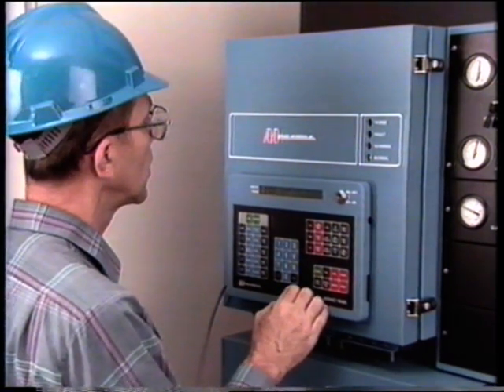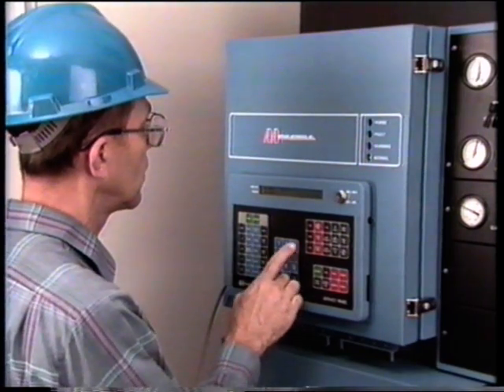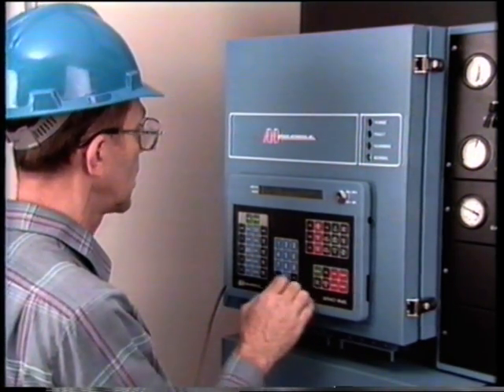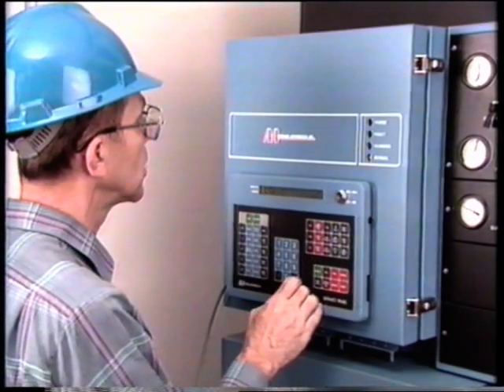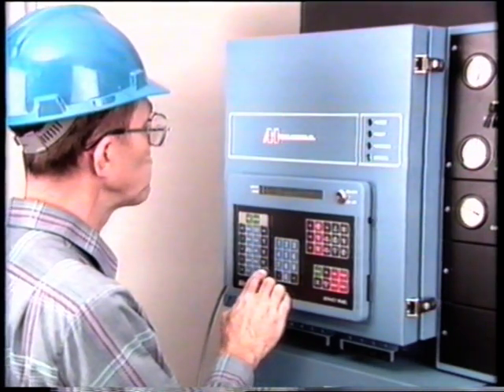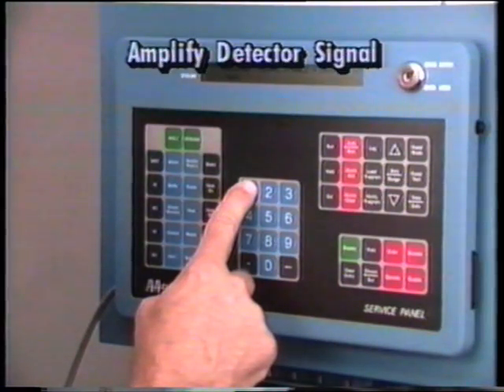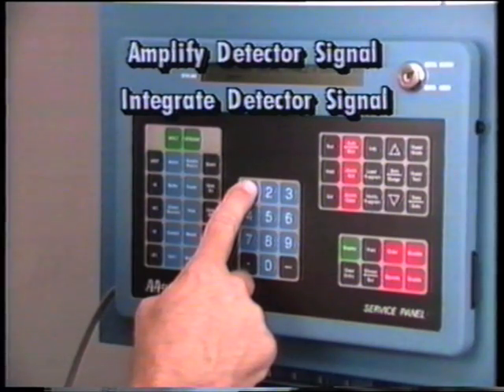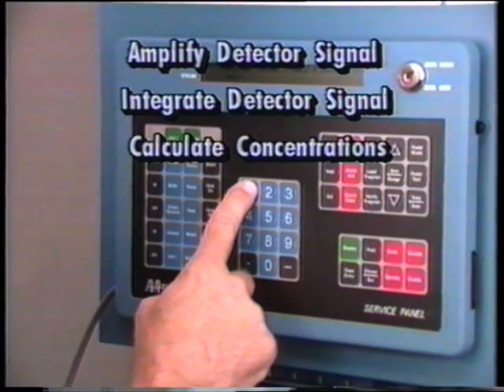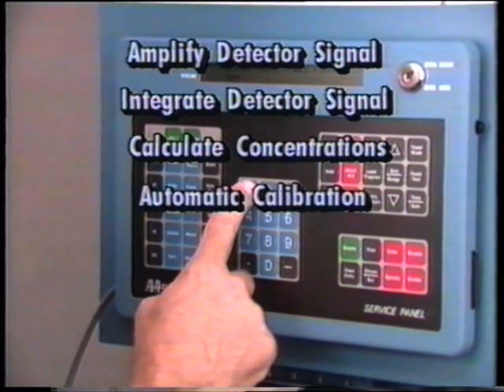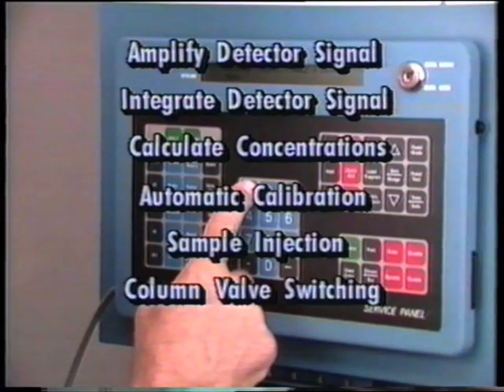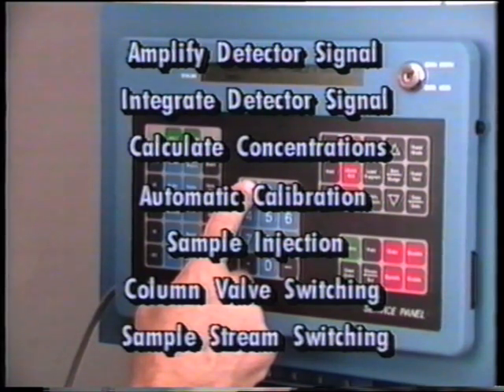Today's microprocessor-based chromatograph control systems are more flexible and easier to use than earlier models. Based on the requirements of a specific application, a gas chromatograph controller can be configured to automatically control certain functions, such as amplifying and digitizing the detector signal, and integrating the detector signal, identifying the peaks, and calculating component concentrations. It is also capable of automatic calibration, sample injection, activating sample and column valve switching on a cycle clock basis, and activating sample switching valves to switch between multiple sample streams or a calibration stream on a sequential basis.